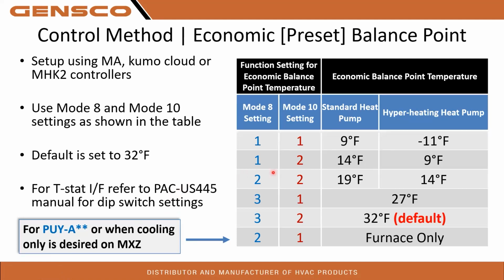Balance points. So I touched base on this a little bit earlier as far as the mode settings and different balance points that this has. So the balance point to switch over from the heat pump to the gas heat is based on outdoor temperature. This will be settings done through your MHK2s, your Kumo Cloud, or your MA controllers, or if you're using a 24-volt thermostat, it's going to be done with dip switches on your PAC 445 interface. Default from the factory is set to 32 degrees ambient outdoor temperature. So once it hits 32, it's going to stop running the heat pump and switch over to the gas furnace. Those settings can be changed using the mode selection in your function settings.